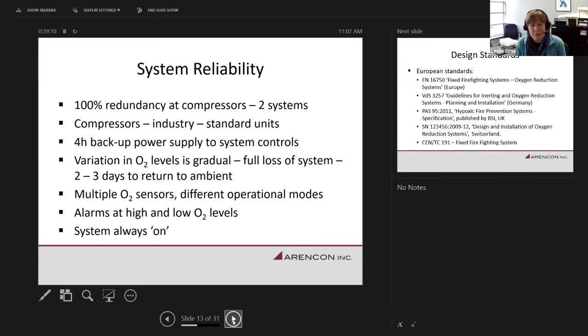Another factor on the system reliability, unlike sprinklers and unlike a gas suppression system, where there's a hard on, a release of a valve, a bang and a discharge, and we've got the fire protection system operational. These oxygen reduction systems take time to get the environment set. So you've got a ramp up time, and in a large warehouse that can take 2 or 3 days to condition the space and get the nitrogen levels at that.